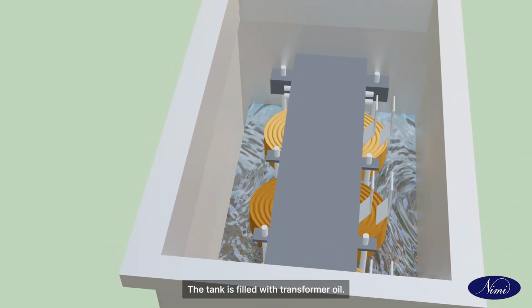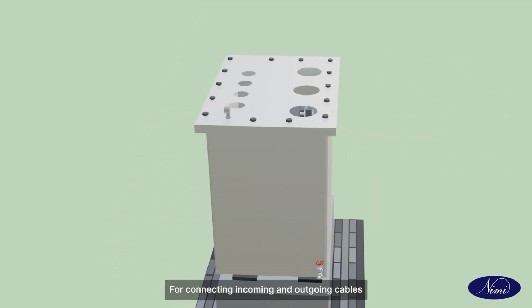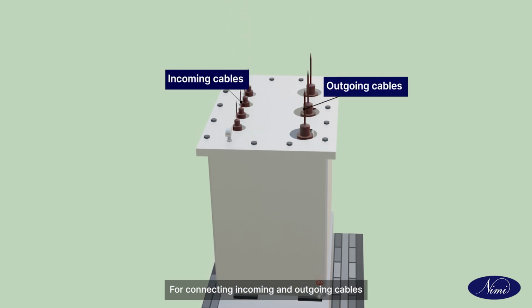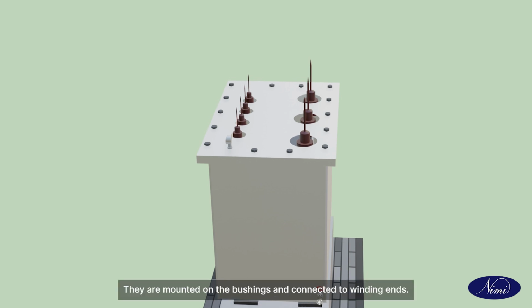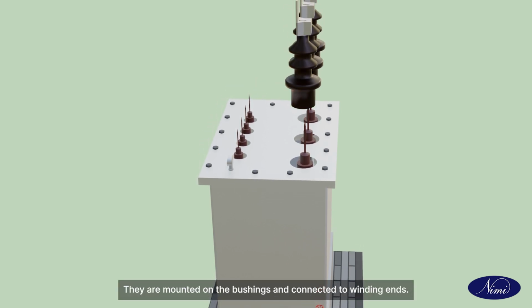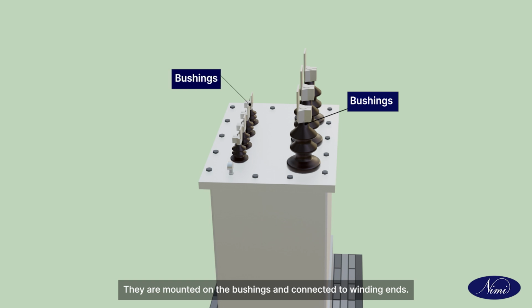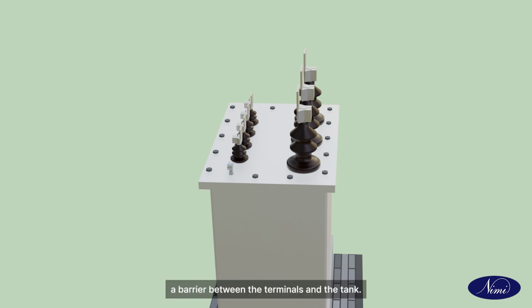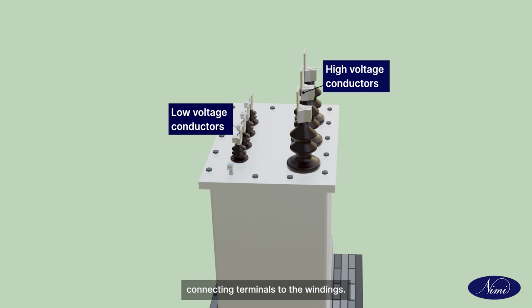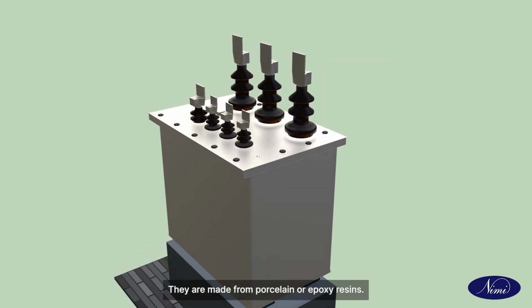The tank is filled with transformer oil. For connecting incoming and outgoing cables, terminals are used in transformers. They are mounted on the bushings and connected to winding ends. Bushings are insulators that form a barrier between the terminals and the tank. They are a safe passage for the conductors connecting terminals to the windings. They are made from porcelain or epoxy resins.